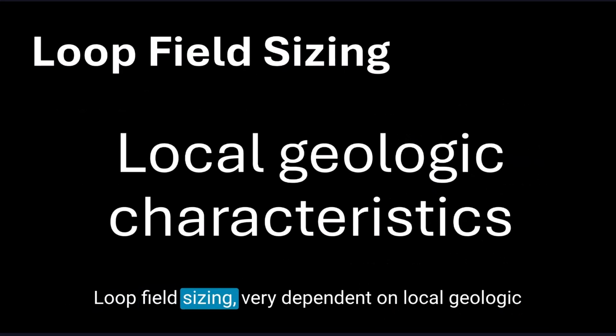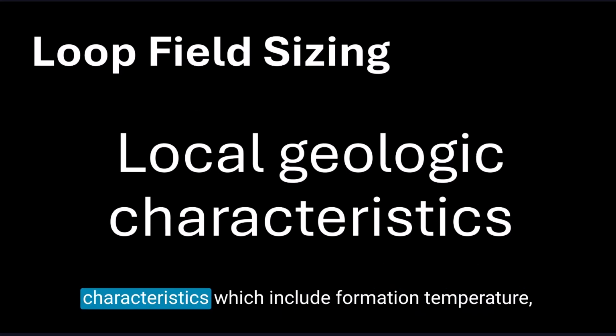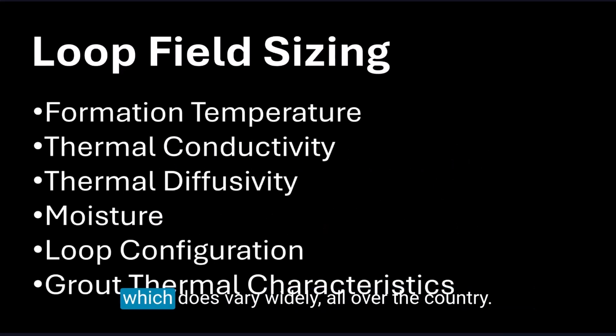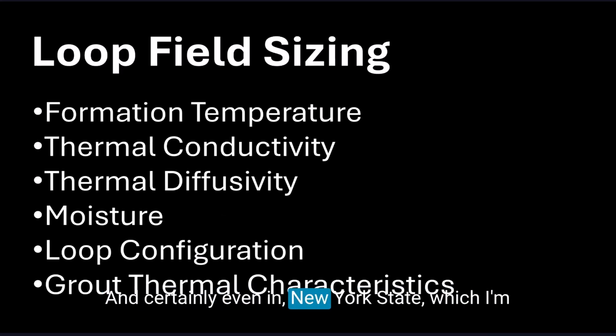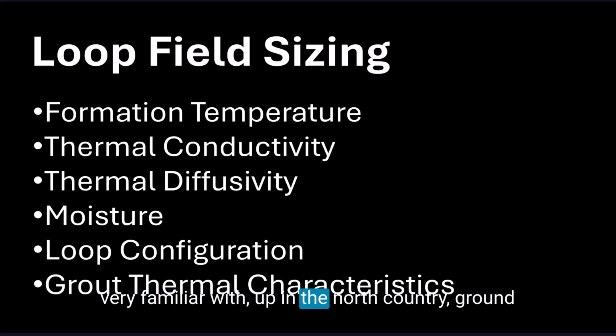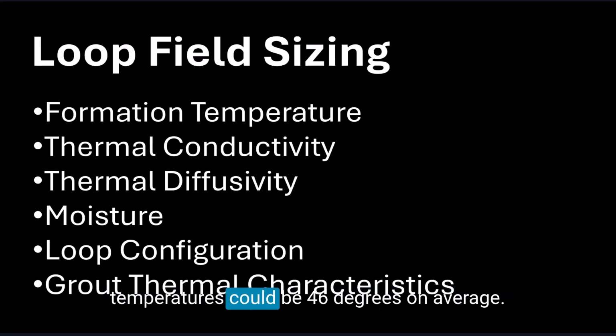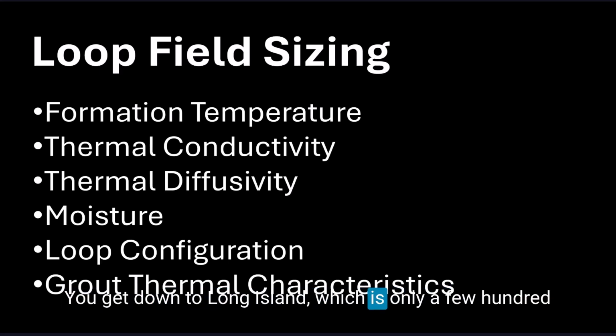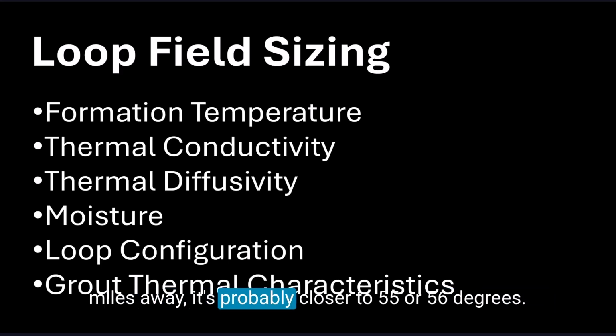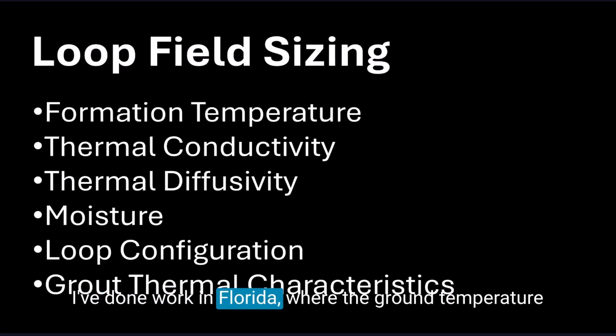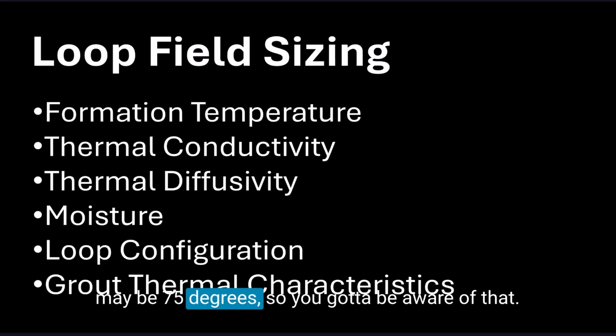Loop field sizing is very dependent on local geologic characteristics and formation temperature. It can vary widely all over the country, and certainly even in New York State, which I'm very familiar with. Up in the North Country, ground temperatures could be 46 degrees on average. You get down to Long Island, which is only a few hundred miles away, it's probably closer to 55 or 56 degrees.